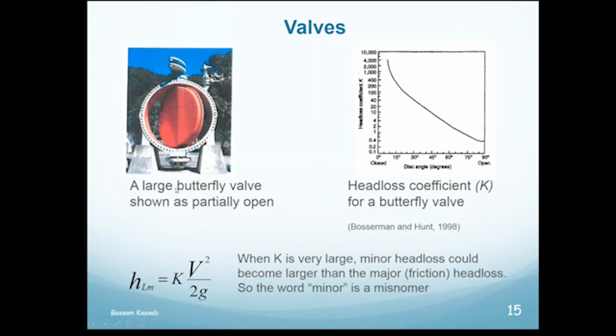This is an example of a big valve. I believe that was a 9-foot valve here, around 3 meters. And you see the butterfly valve, how it turns. So when it's totally open, if the red disc is here, the losses will be less. But as you close the valve and the flow is passing through, it has a more difficult time to pass through, so the K value becomes larger and larger.